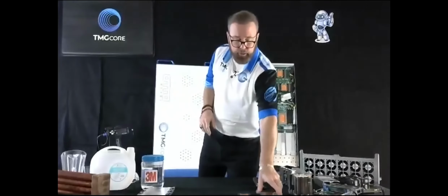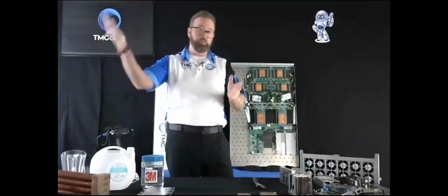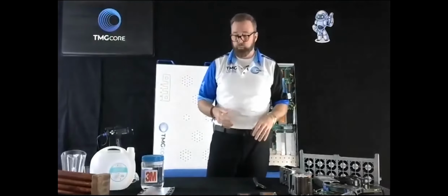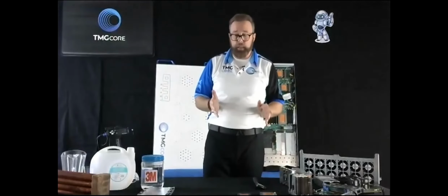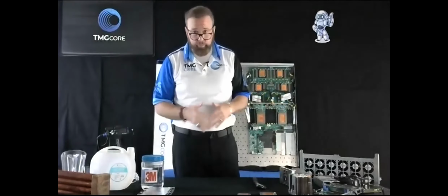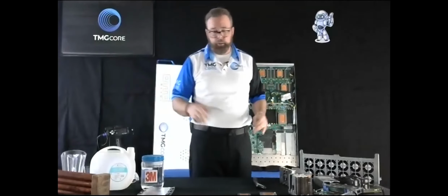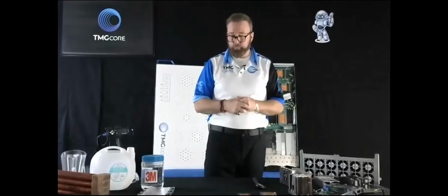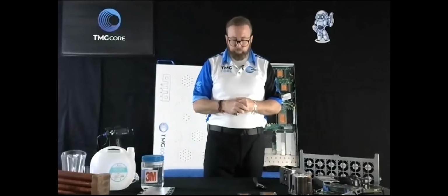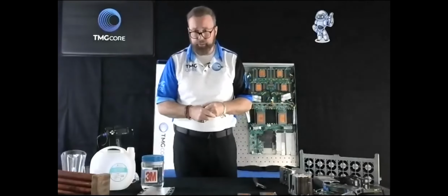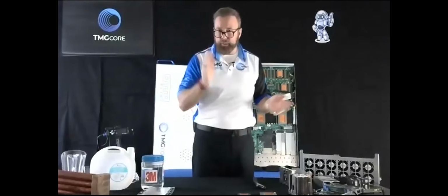Then you have the rear door heat exchanger, which is basically a heat exchanger on the rear side of a rack. One of the best companies making those is Vertiv - they make a phenomenal rear door heat exchanger product. I recommend it if you're interested in deploying one, and you can get some pretty significant densities, in some cases 50 kW per rack.